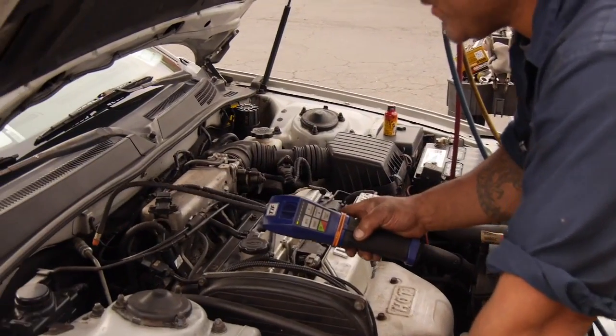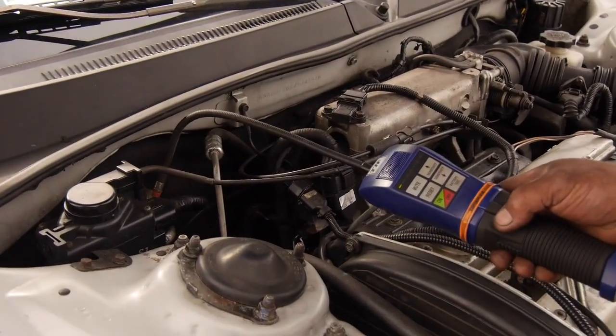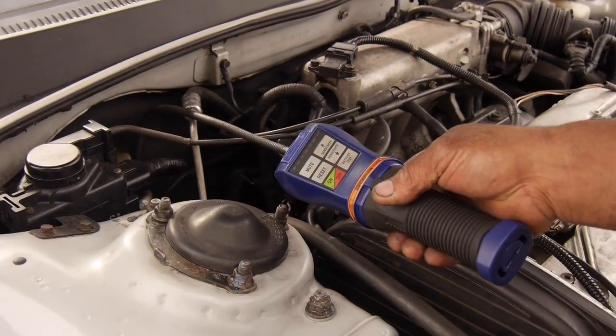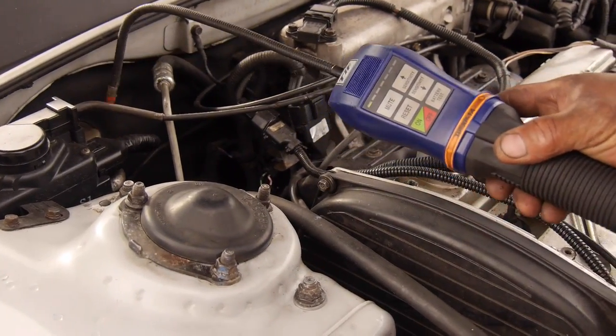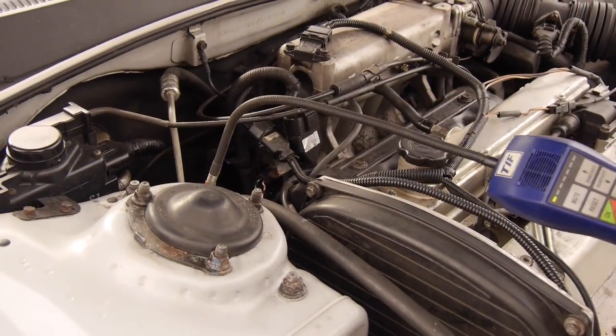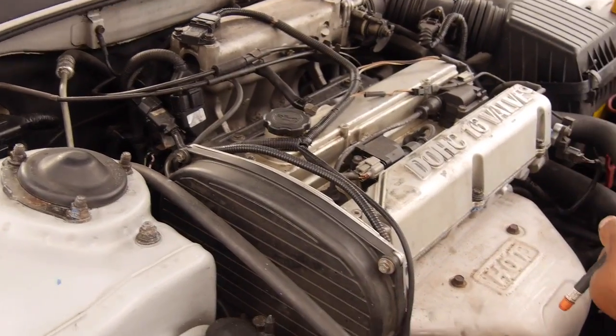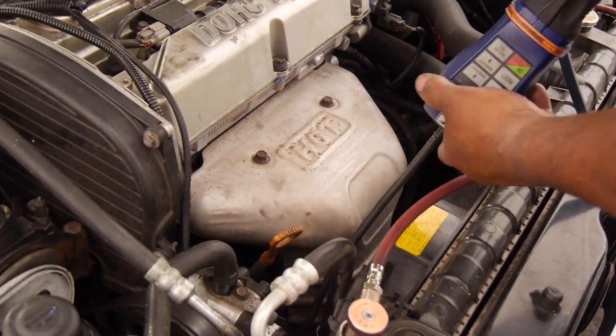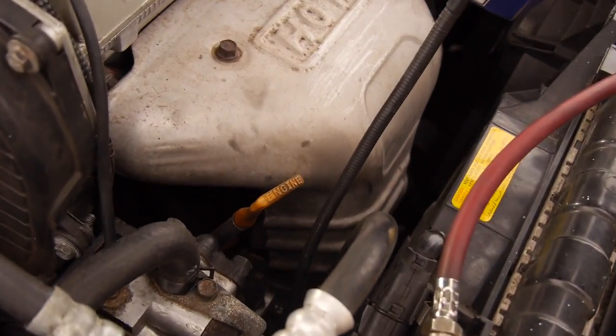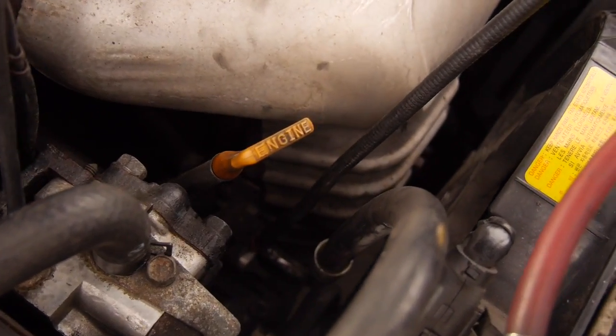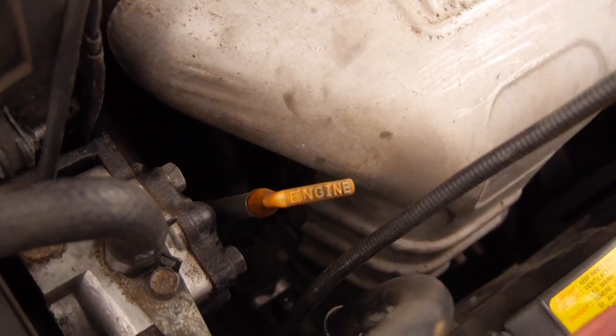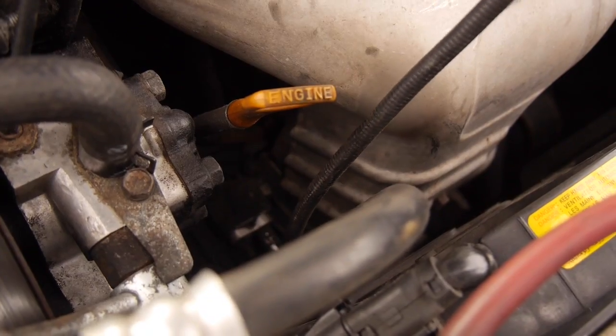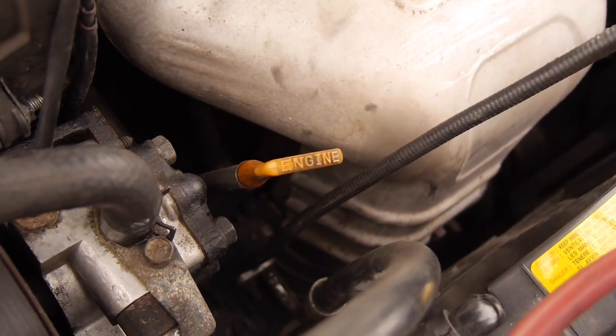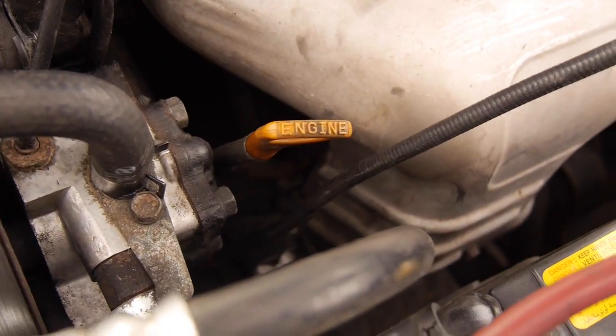You want to stay on the system, the low side line, the thermostatic expansion valve. You want to check for a leak and find it. You could go down to the compressor, these are the connections to the compressor. It's sniffing, looking for leaks. If the compressor's leaking, it will make this type of noise.